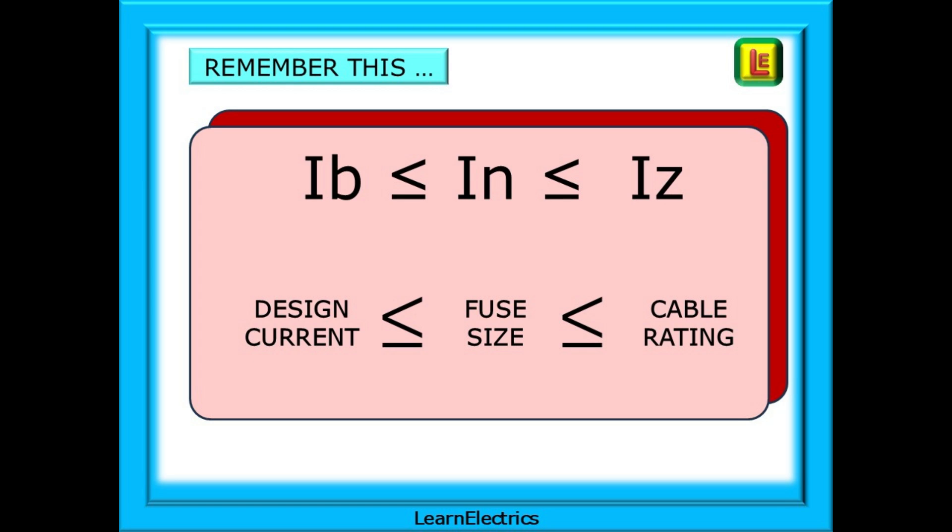Remember this, it matters. The design current must be less than or equal to the fuse or breaker size. And the fuse size or breaker size must be less than or equal to the cable current carrying capacity for the circuit.